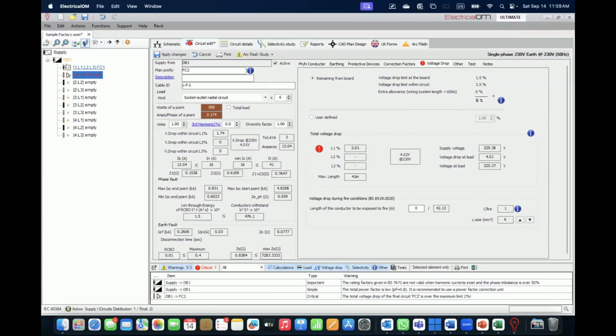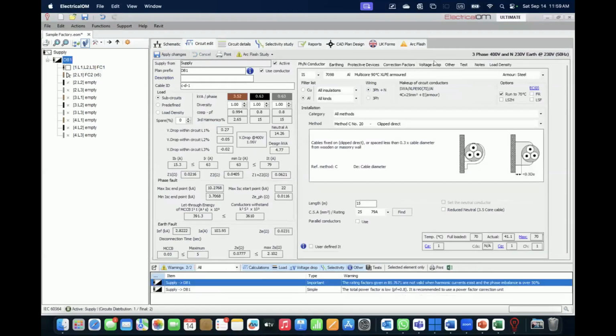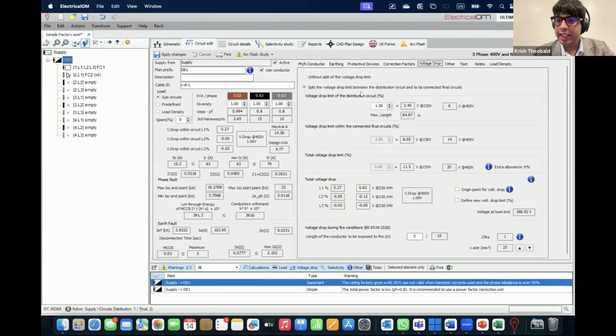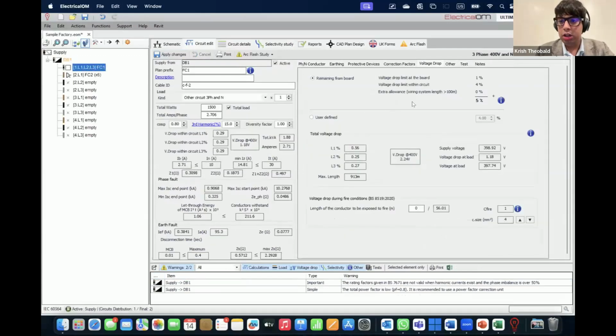If I go to the board now and select voltage drop, here I say 1.5%. If I change this to 1% and go back here, now I see 1 and I get 4% here. So it is entirely dependent on whether you want to set it individually for the load, for the final circuit, or you want to set it for the board. It's up to you how you want to set it. That is okay. It's clear.